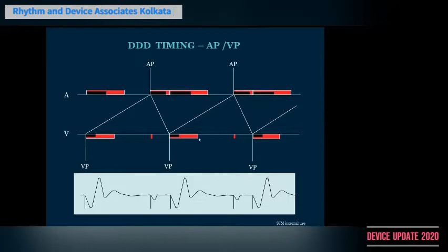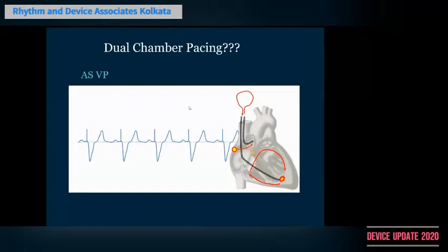So what is ASVP? ASVP is something that is always preferable and very commonly seen. The atrium senses an intrinsic P wave, and at the end of an atrioventricular interval, which is pre-specified by the programmer, the ventricle gives a spike and the ventricle is captured by this. So basically you are tracking the atrium. This is called a tracking mode. So you have an atrial sensed event, and after an atrioventricular interval, the ventricle searches; if there is no intrinsic ventricular event, a ventricular pacing spike is given and your ventricular timing cycle starts.